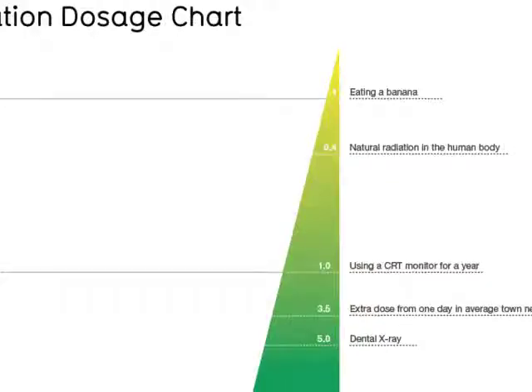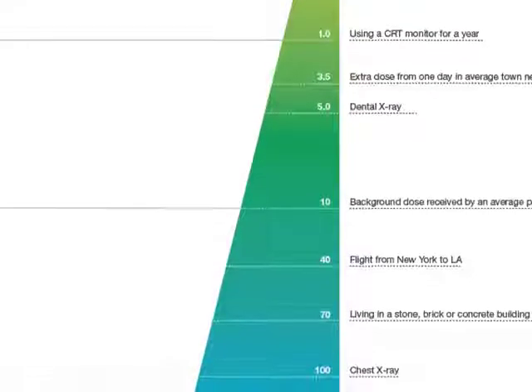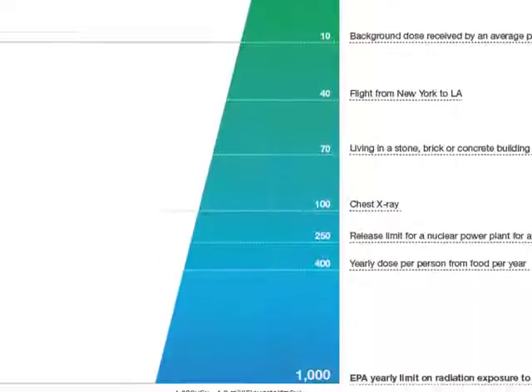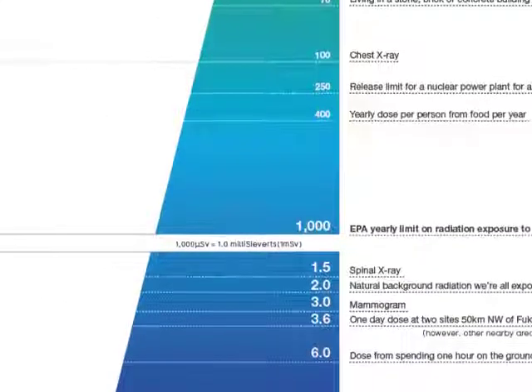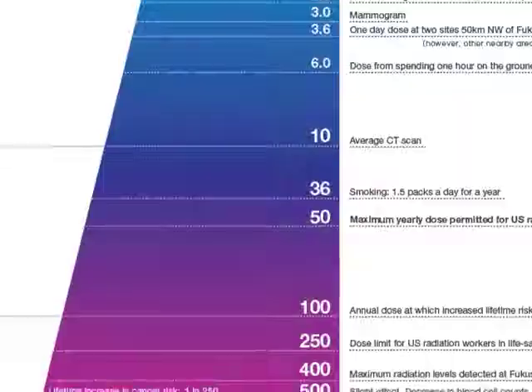Calibrated equipment accurately measures the level of radiation, giving a result in Sieverts or some other unit, providing a dosage the human body is being exposed to or absorbing. The uncalibrated detectors in this video simply indicate the presence of radiation.